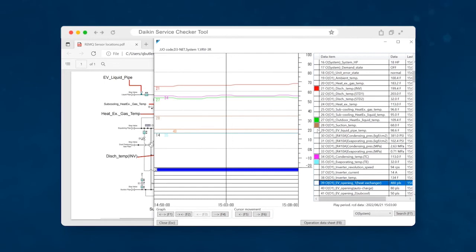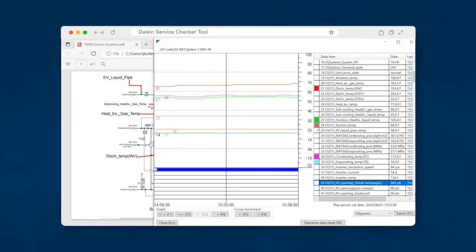If you have a number that's below that discharge superheat range of 27 degrees, then you need to start looking for a flood back condition. And so, how does oil get washed out in the first place? Generally, liquid refrigerant flooding back to the compressor. And so, at that point, you need to start looking at your indoor unit expansion valves, go through and shut each one of them off and see if any of them bleed by.